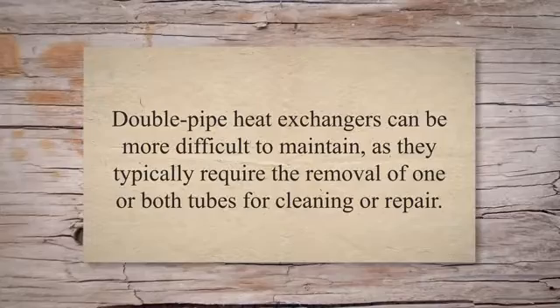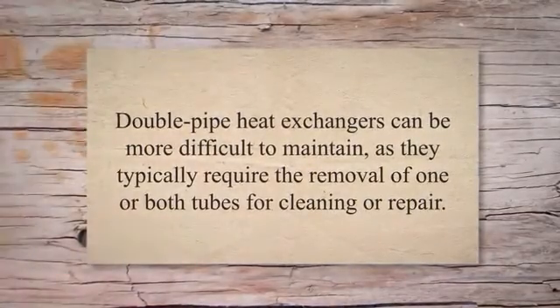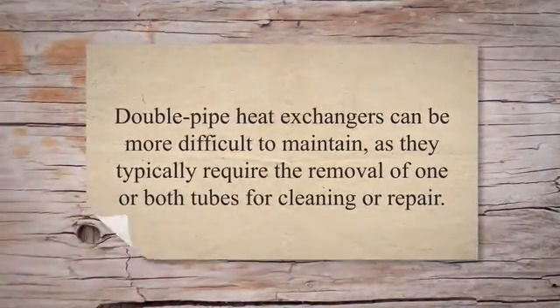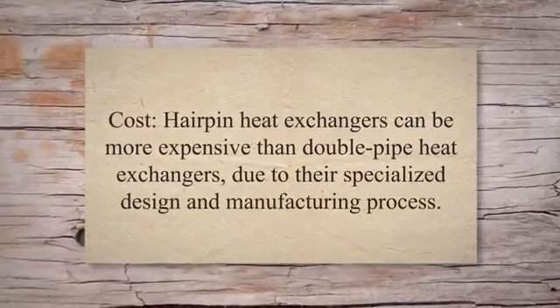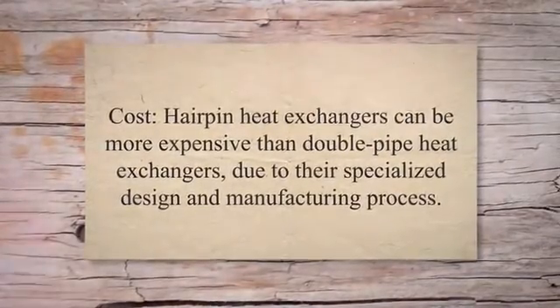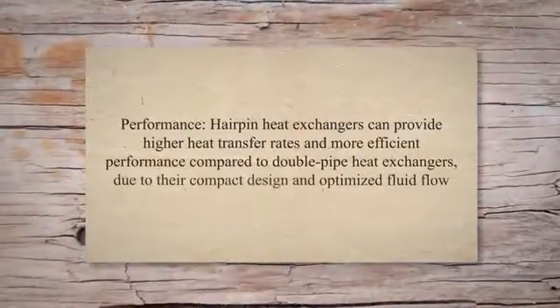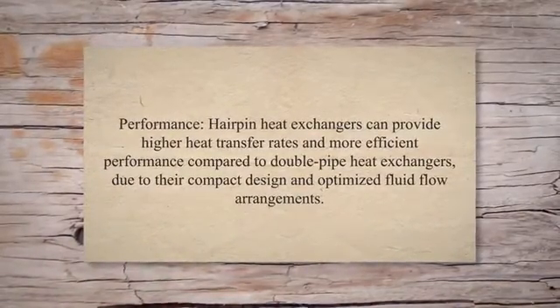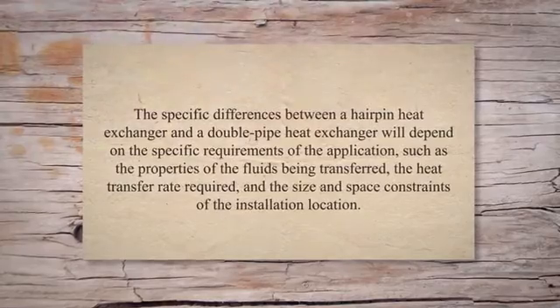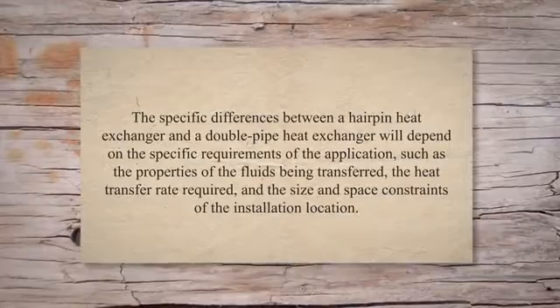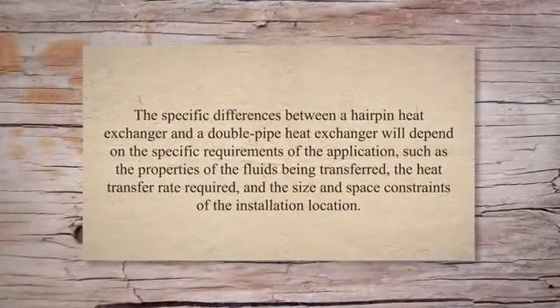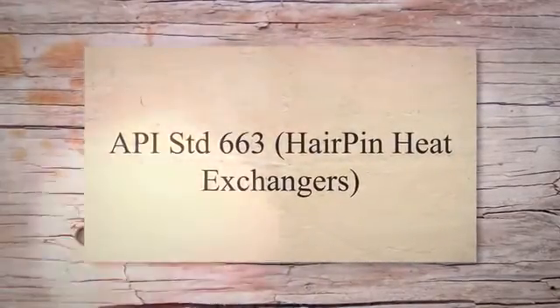For maintenance, hairpin heat exchangers are designed for easy disassembly and cleaning, while double-pipe heat exchangers typically require removal of one or both tubes. Regarding cost, hairpin heat exchangers are generally more expensive due to their specialized design. In terms of performance, hairpin heat exchangers can provide higher heat transfer rates and more efficient performance compared to double-pipe heat exchangers due to their compact design and optimized fluid flow arrangements. The applicable standard for hairpin heat exchangers is API Standard 663.